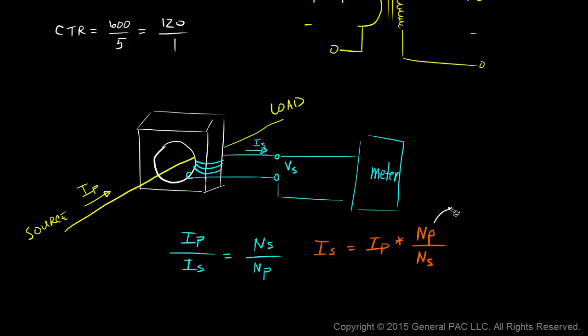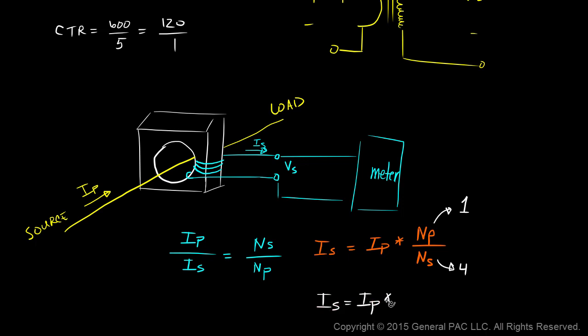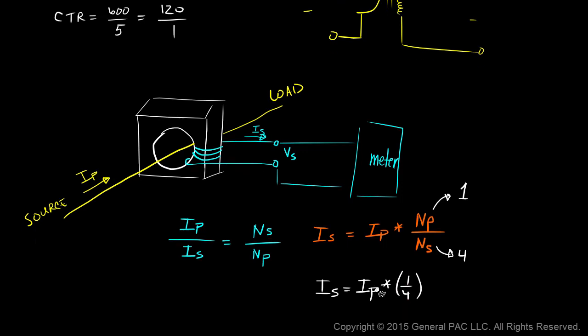The number of primary turns is simply 1, because the conductor goes directly through the transformer — essentially one turn. The number of secondary turns is 1, 2, 3, 4 — so four turns. Therefore, secondary current equals primary current times 1/4, meaning the secondary current is one-fourth of the primary current.